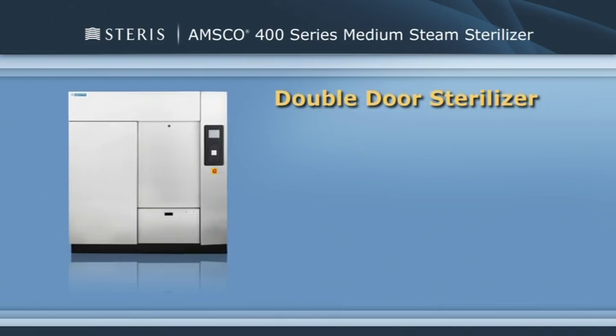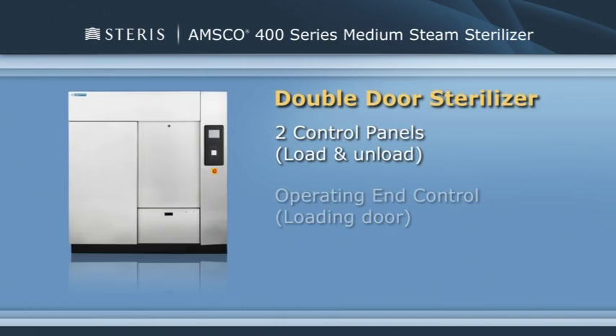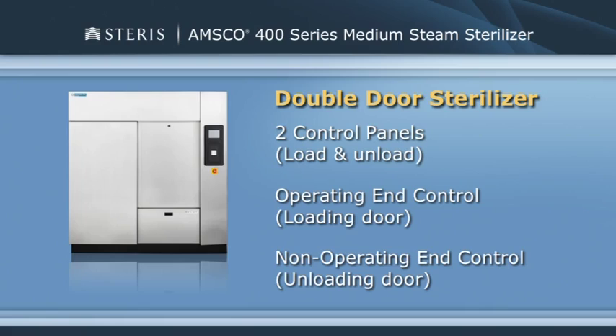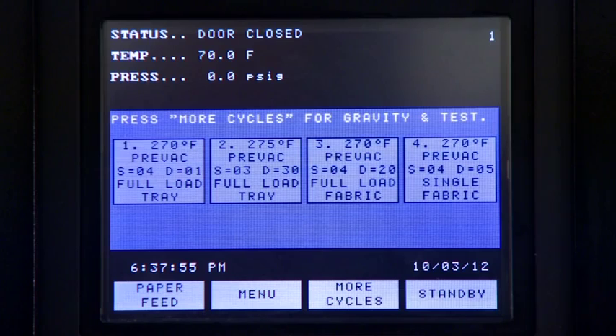A sterilizer equipped with 2 doors will also be equipped with 2 control panels. The control panel at the loading door is referred to as the operating end control. It's used to select and start cycles, abort cycles, set cycles and cycle values, and obtain status printouts. The control panel located at the unloading door is referred to as the non-operating end control. Except for the presence of the printer, control panels at both ends of the unit are similar, and each can be used to start or abort the sterilizer.